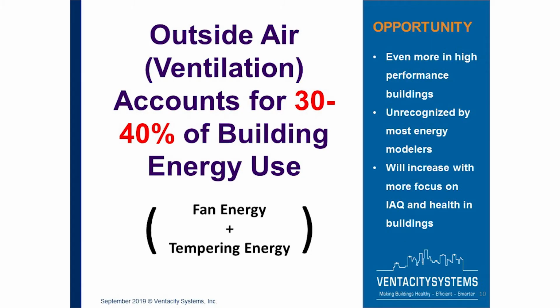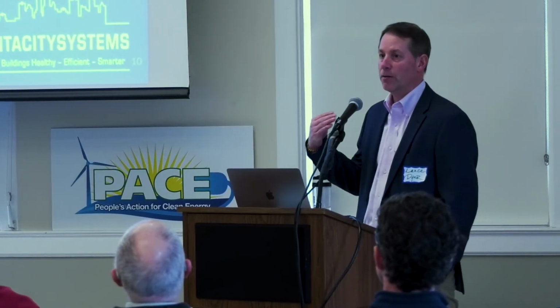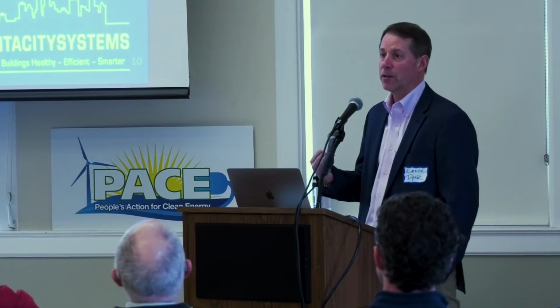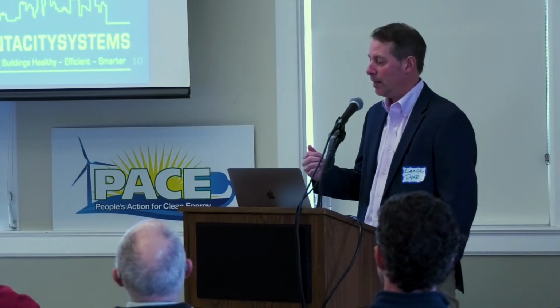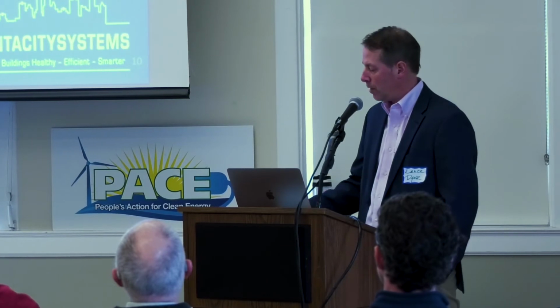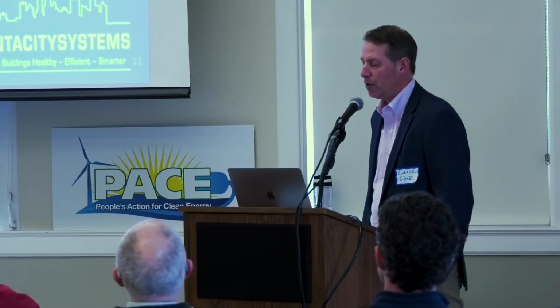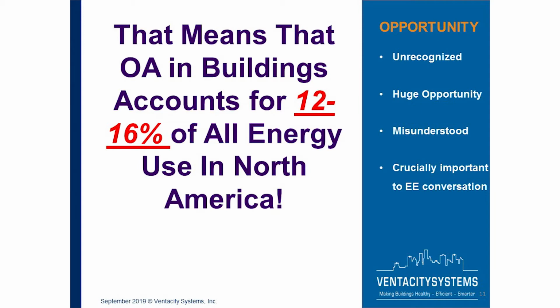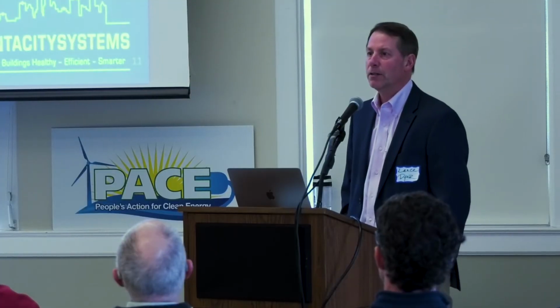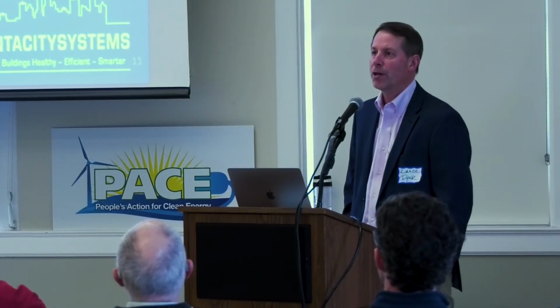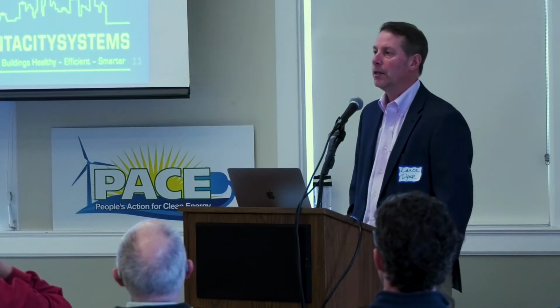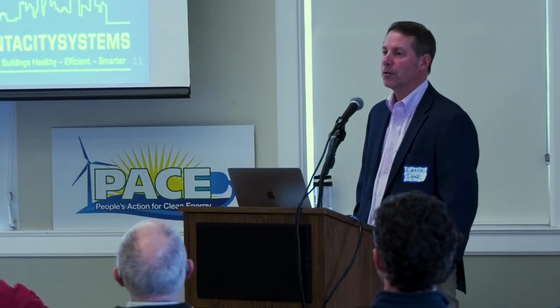Of all of that, outside air ventilation accounts for 30 to 40% of the building energy usage. And that's a combination of the fans and what it takes to temper the air. And the next slide will show a little bit more of what we're talking about as I get into this. So that means that outdoor air in buildings accounts for 12 to 16% of all energy use in North America. Nobody really thinks about that, about ventilation and how you move fresh air from outside into the building. But that's a lot of energy being used in order to do that.